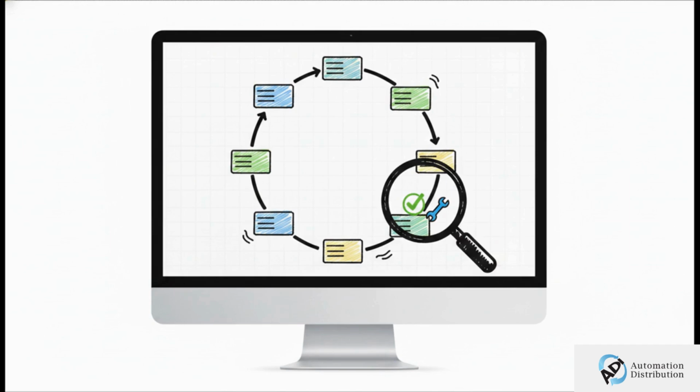Instead of forcing you to parse complex logs through some intimidating command line interface, WAGO gives you a visual, browser-based, web-based management tool, or WBM. It literally streamlines the parameter set to exactly what a controls team actually needs. You get a live topology map of connected devices, per-port usage monitoring, and crystal-clear visual error diagnostics. If something goes wrong, you're looking at a clear map of your network, not miles of code. It totally empowers maintenance teams to stand up a redundant ring without needing a dedicated IT engineer looking over their shoulder.